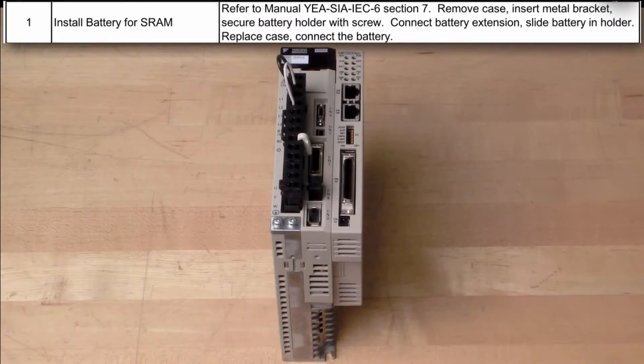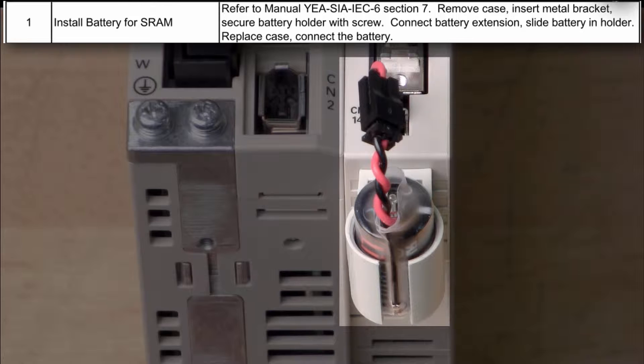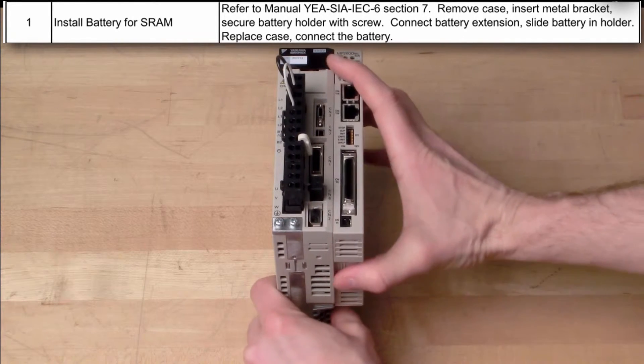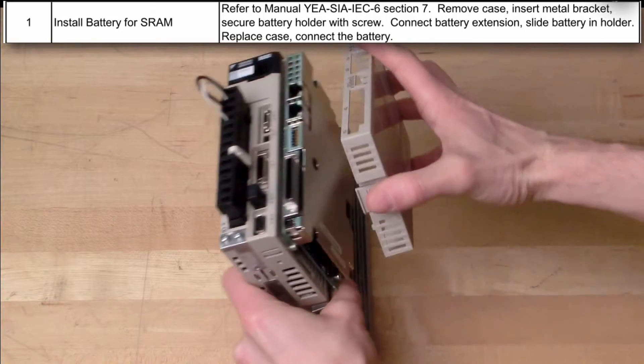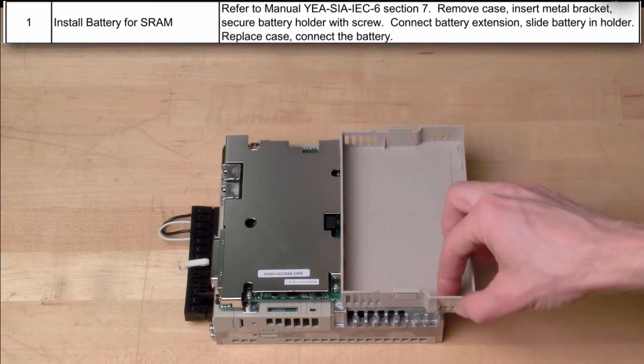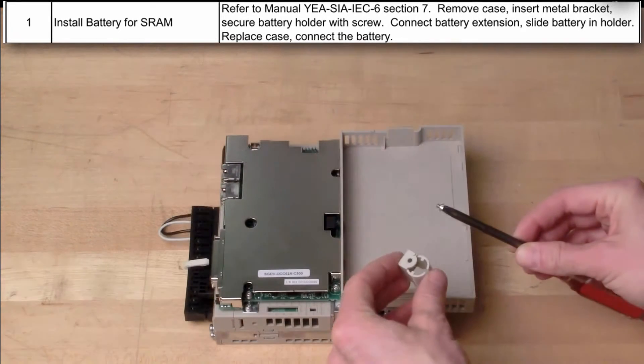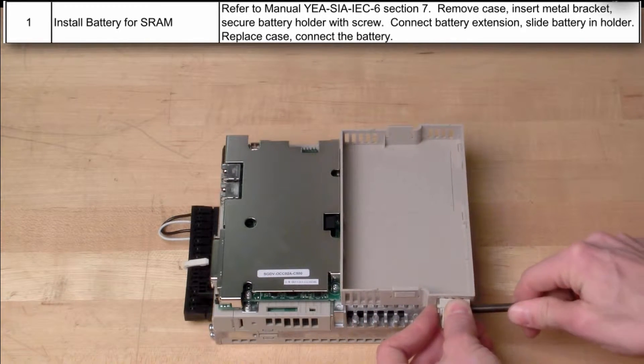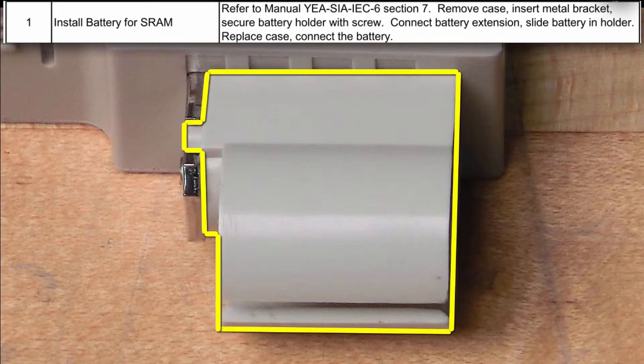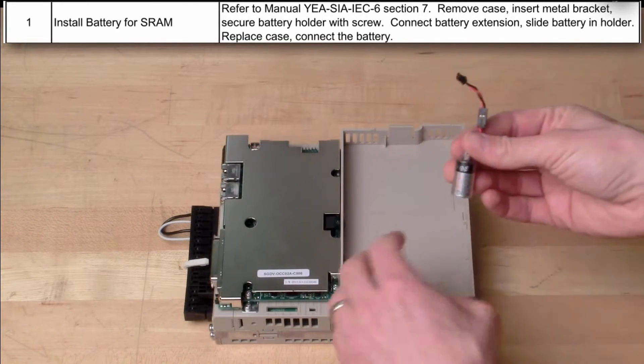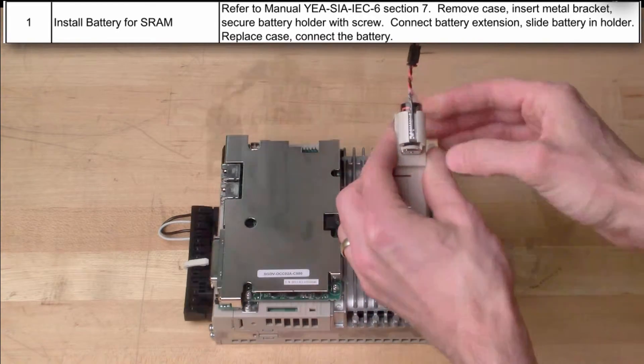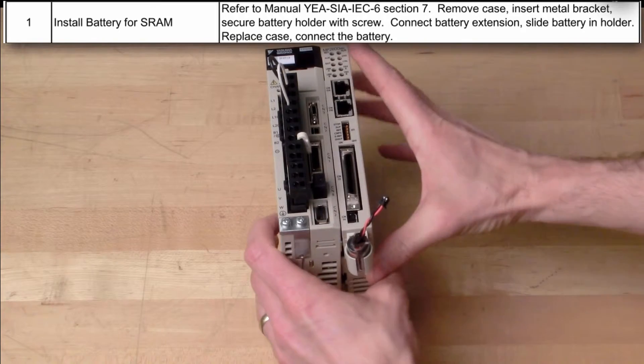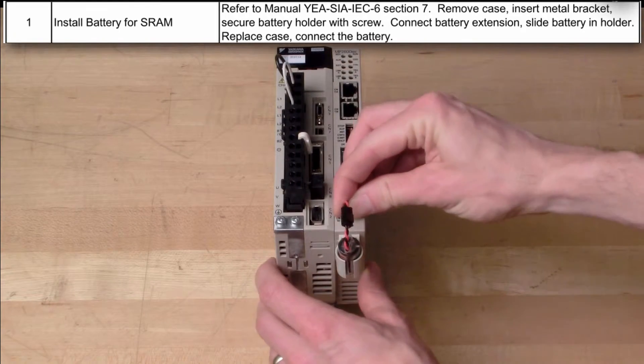The MP2600IEC comes with a lithium battery for the SRAM that must be installed. Squeeze to remove the case, insert the bracket, and secure the battery holder with the screw. Connect the extension and slide the battery into the holder. Snap the case back on and connect the battery.